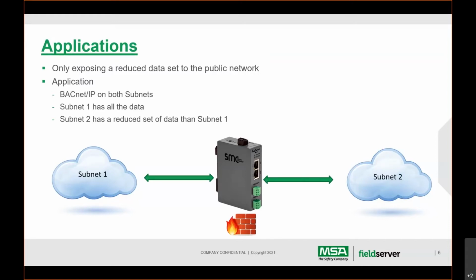We've had applications in the past where you've got a BACnet IP network all set up and working well, which is the control network, and then you have the public network with operations staff. They typically won't want all those BACnet objects exposed to people within the organization, because they start to change different BACnet objects, which could pose issues. So you might just have your temperature set point and main mode available, a couple of BACnet objects, while the rest are kept behind the field server.